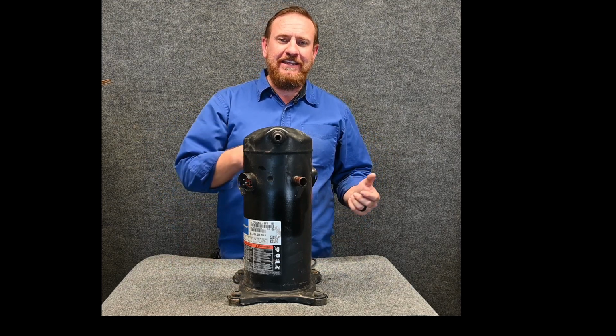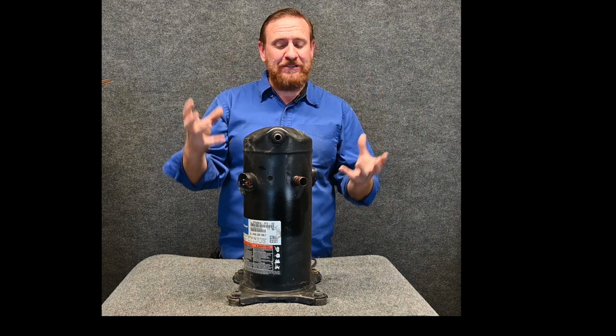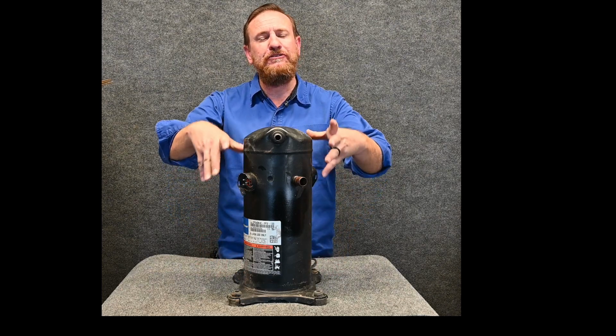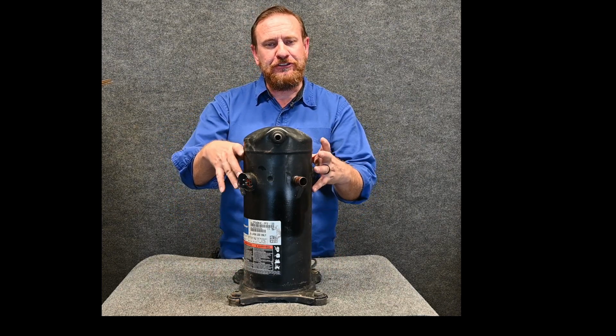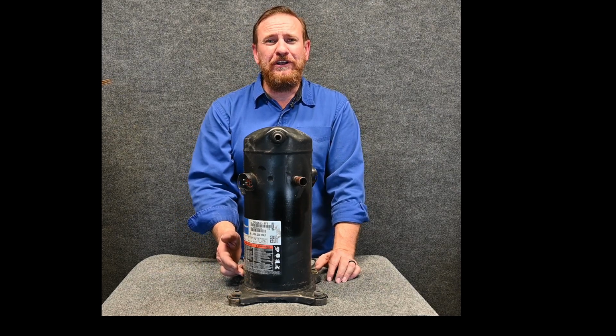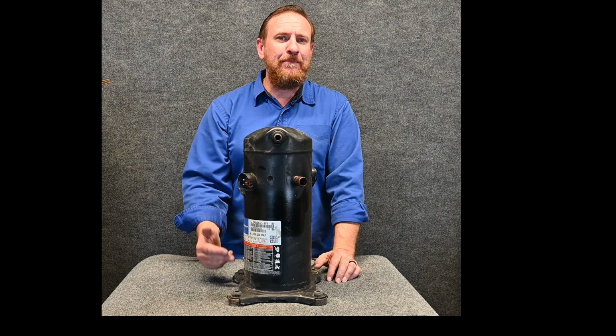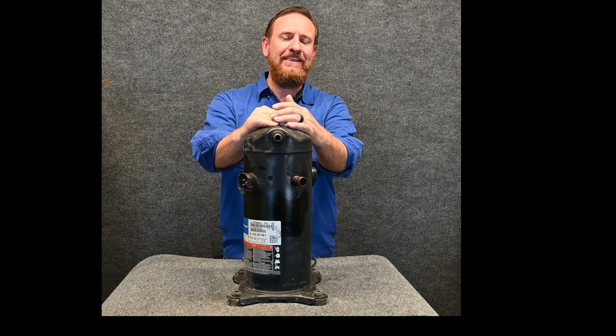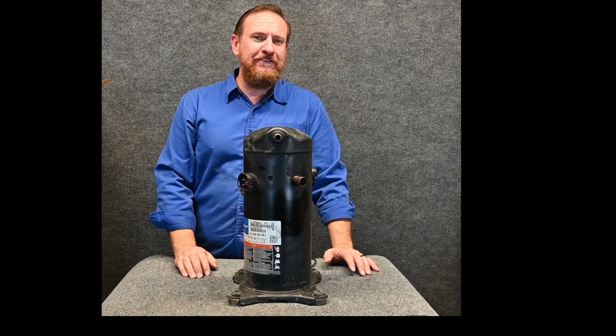If you've ever blown bubbles, that's what's happening. All this foam, all these bubbles. So the oil level starts to drop as all this foam starts rising. Well, as all this foam starts to rise, we have two problems. Problem number one, we end up at the bottom with no oil to lubricate those bearings. And problem number two, we get all the oil into the pump action. So that's a very bad thing. So we want to make sure that we prevent that from happening.